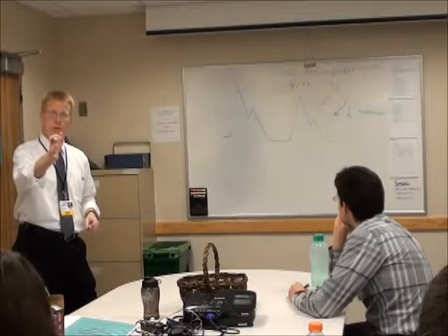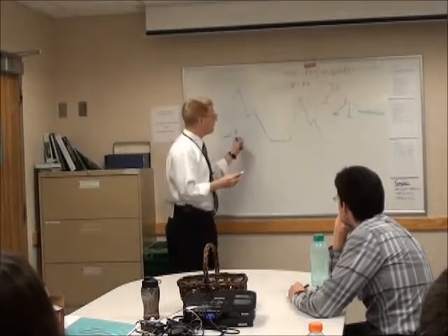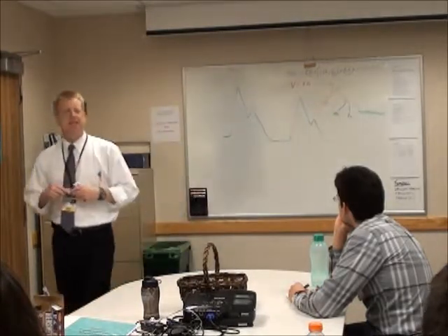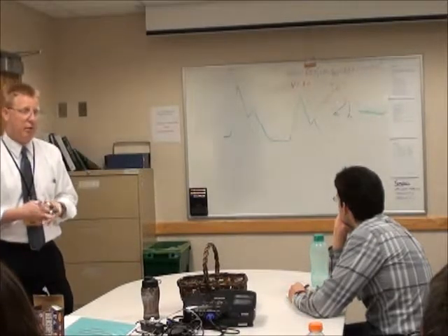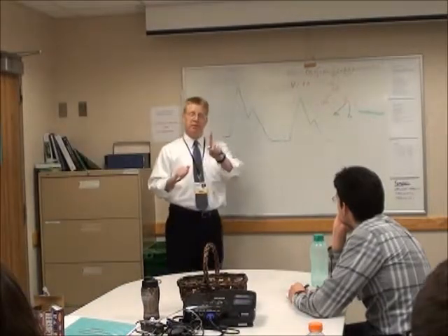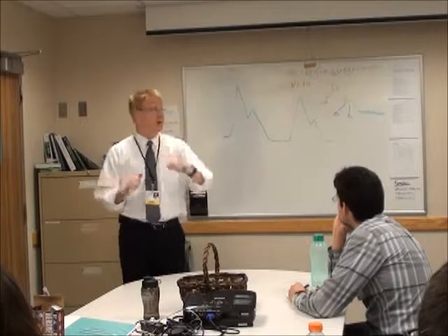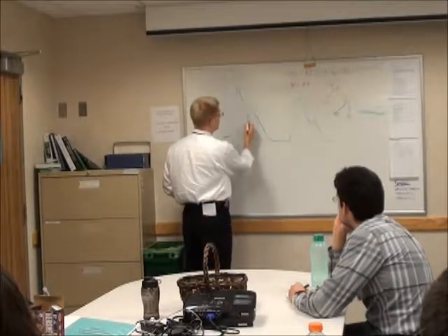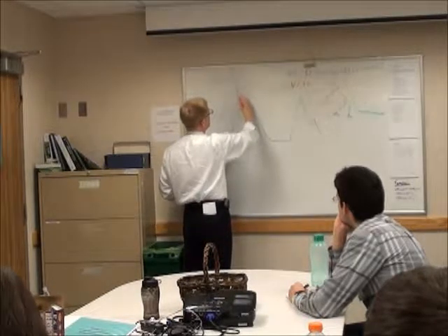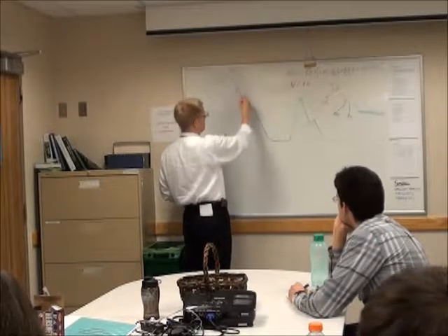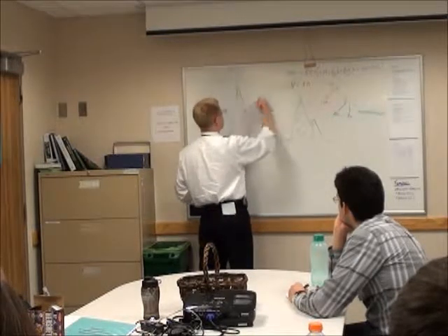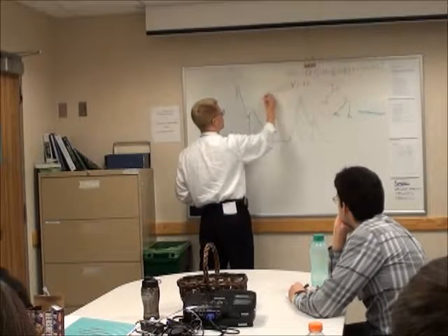But if that wasn't enough money for you, you hooked up the FloTrac. Okay? So how does it decide what a stroke volume is? It doesn't. It makes up a number. Totally makes it up. But it makes it up in a rational way. Thus said complicated calculation. But what it's really doing is paying attention to a point just past the dicrotic notch, and it's measuring a surface area. It's measuring the volume under this curve, and then it does it for here too. This volume is proportional to a stroke volume.